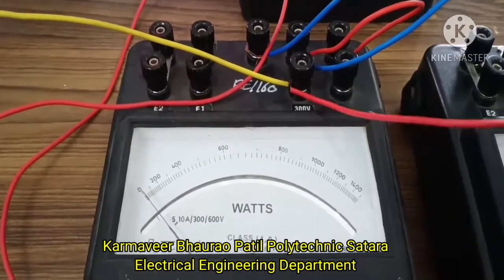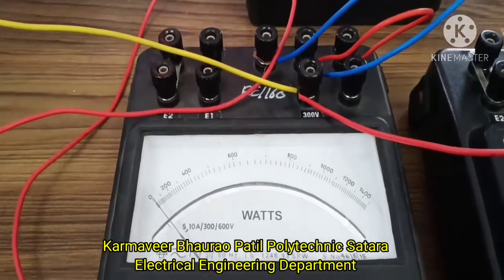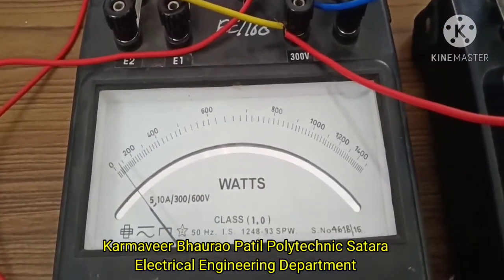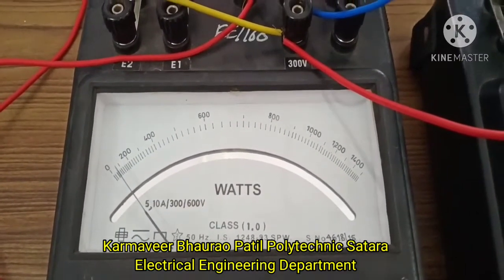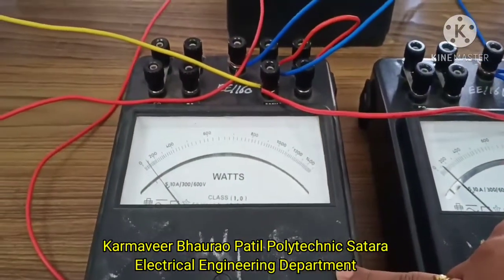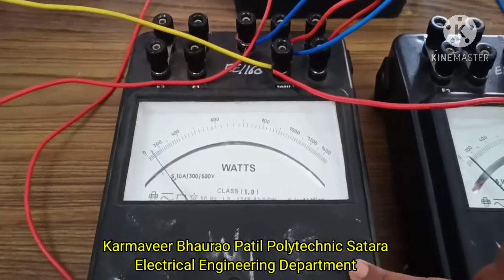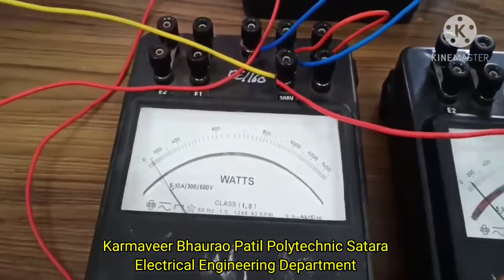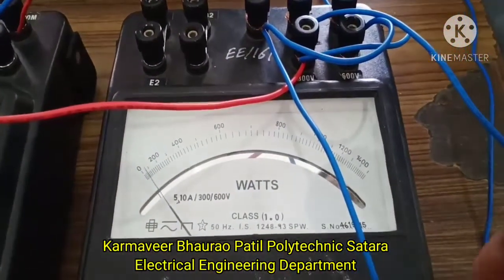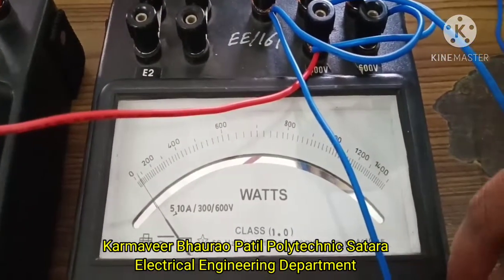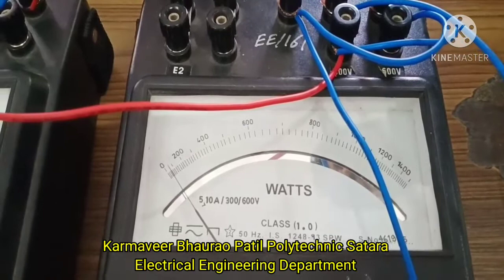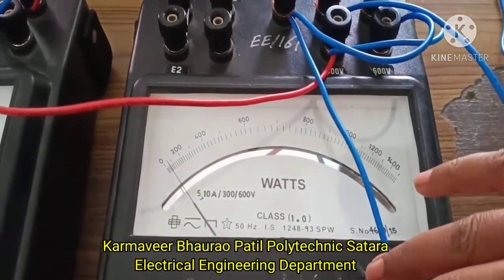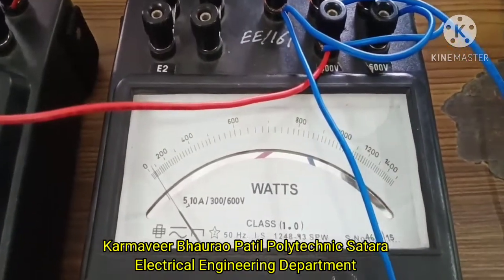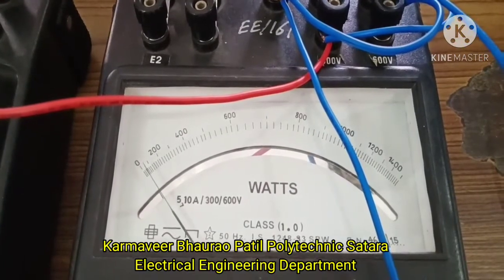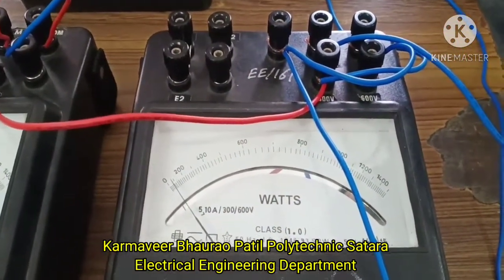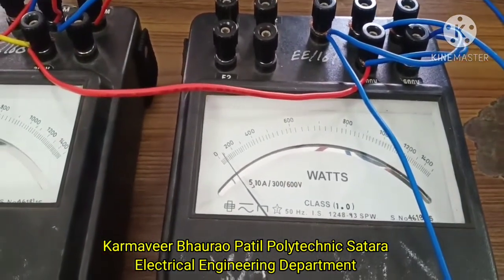Now it is showing negative. Wattmeter 1 is showing near 50, and the multiplying factor for this W1 is 4. So 50 into 4, that is 200 watt we are getting for W1. Next we will observe the W2 reading. Here we are getting the same. This wattmeter also has a multiplying factor of 4. So 50 into 4, that is 200 watt. So both wattmeters are showing 200 and 200 watt.